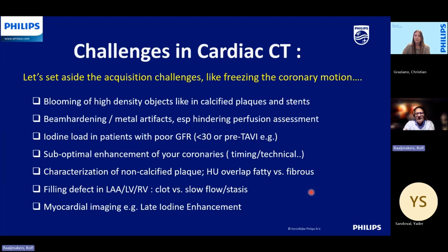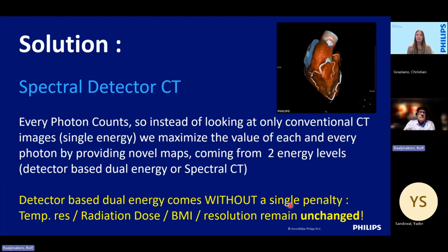by definition with a 16 centimeter or a fancy scan mode, whatever. This is all linked. All the things that I discussed here are linked to the single energy nature of conventional CT. So what is the solution? Well, the solution is spectral detector CT. Every photon counts, so instead of looking only at conventional single energy CT, we maximize the value of each and every photon by providing novel maps coming from two energy levels, a high energy level and a low energy level.